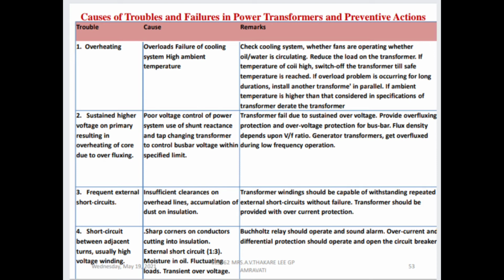Fault means what, and their causes and then remedies. Causes for this: insufficient clearance on overhead lines, accumulation of dust on insulation. And the remark is, transformer winding should be capable of withstanding repeated external short circuits without failure. Transformer should be provided with overcurrent protection. Then fourth is short circuit between adjacent turns, usually in high voltage winding. Causes are sharp corners on conductors cutting into insulation, external short circuit, moisture in oil, fluctuating loads, transient overvoltage. Then remarks are, Buchholz relay should operate and sound alarm. Overcurrent and differential protection should operate and open the circuit breaker.